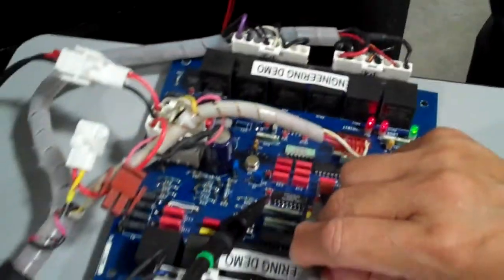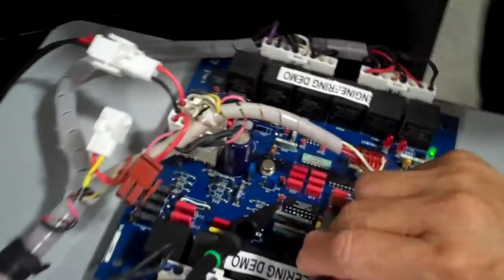Okay, go ahead, Tony. Now, we can also take a look at the ultimate output of the phase loss detection circuit, either at CR3 or at J6 position 5. In this particular case, we're going to be looking at R43.